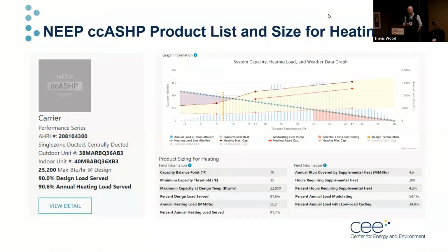This graph really addresses something we call the Goldilocks zone, which is this gold area here. This is the maximum heating capacity of this Carrier unit, and this is the minimum heating capacity. It's inverter driven and designed to work in cold climates, so anywhere in this space, this piece of equipment is always capable of adjusting itself to the outdoor temperature to make sure it's meeting the load.